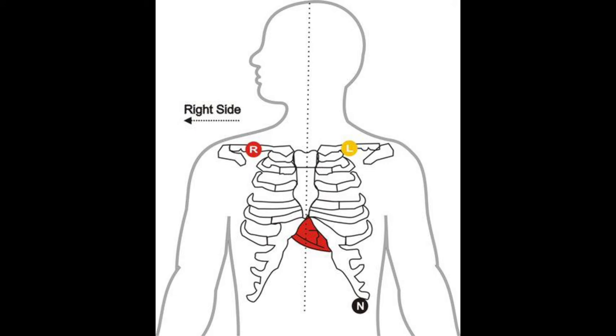The first lead will be placed under the clavicle on the right side of the heart. The second lead will be placed under the left clavicle at the same height as the first one. The last lead will be placed on the left side of the heart on the lower edge of the left ribcage.